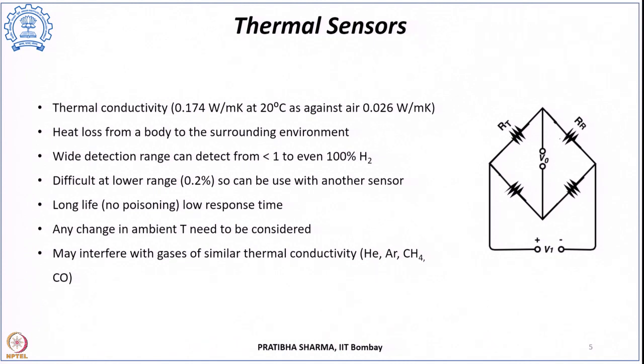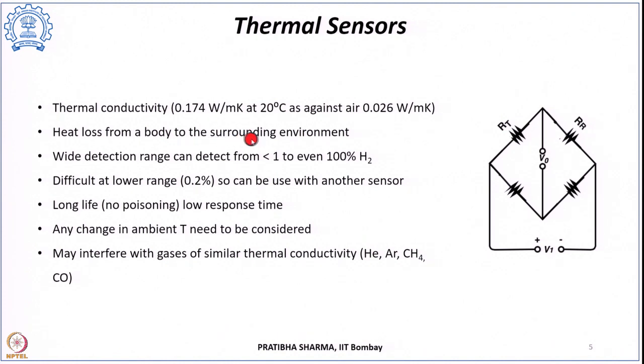The first type is the thermal sensor, which is based on thermal conductivity. The thermal conductivity of hydrogen is higher than that of air — at 20°C, hydrogen's thermal conductivity is 0.174 W/m·K while air's is 0.026 W/m·K. The principle is based on heat loss from a sensing element to the surrounding gas, and the extent of heat loss depends upon the thermal conductivity of the surrounding environment.